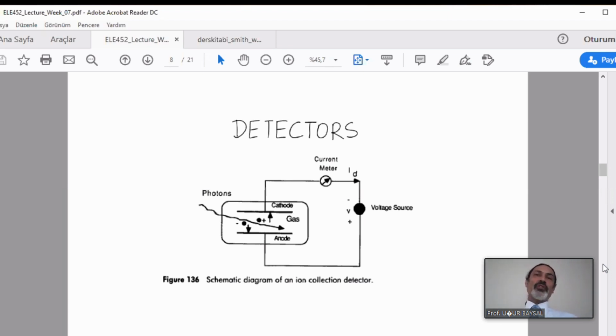The most important parts of these instrumentation systems are their detectors and their computers. Detectors: that means we have to capture 511 keV photons, and capture them efficiently. That means you have to capture all photons, but you have to be careful not to capture scattered photons. You specifically have to capture 511 keV oppositely traveling photons.